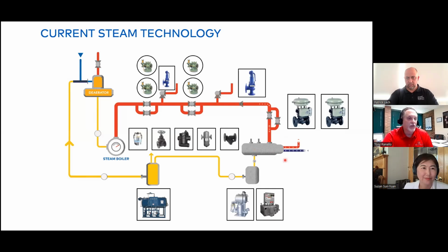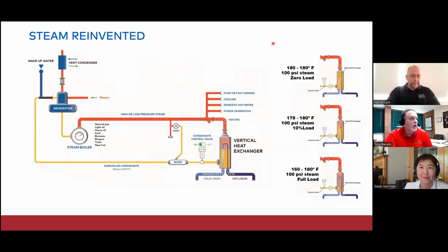We've got a conventional heat exchanger over here. This would be a steam to water heat exchanger with 1/3, 2/3 control valves. And then we've got our typical steam trap to a condensate receiver, which is vented. That can either be an electric or a steam motive type condensate receiver, maybe going then to a master receiver, which eventually pushes everything back to the deaerator. And then the whole cycle starts again, feeding water to the steam boiler. So that's pretty much, in a nutshell, what we do today. Let me show you what we feel is the way to really look at this.